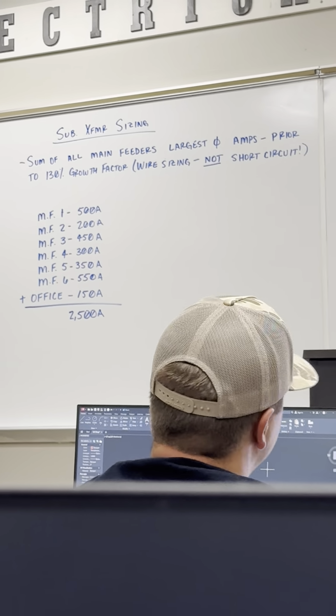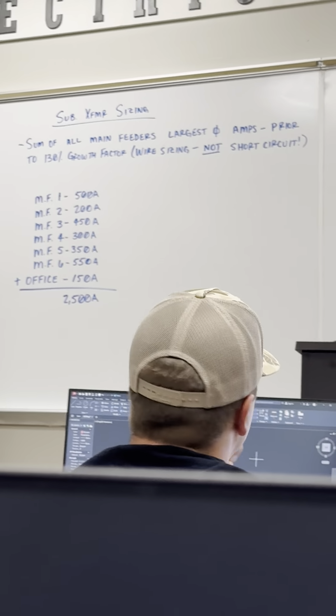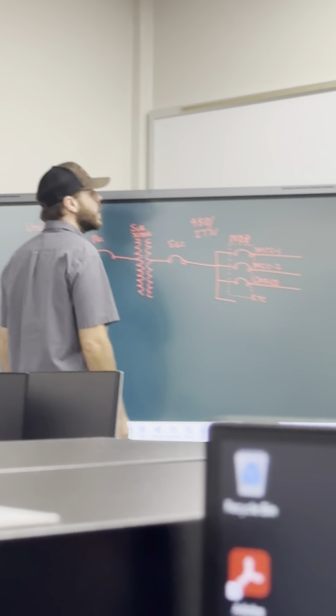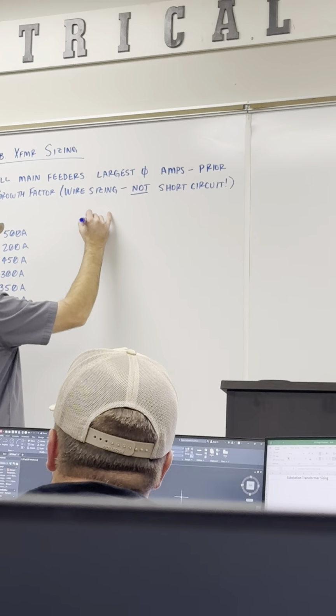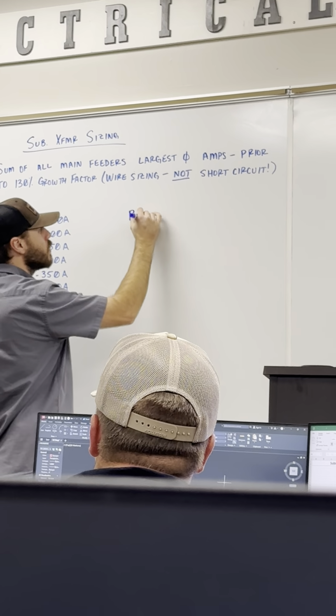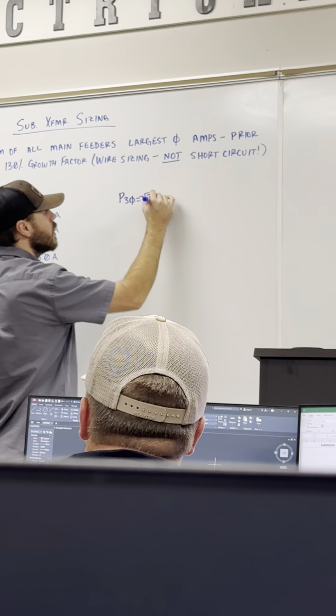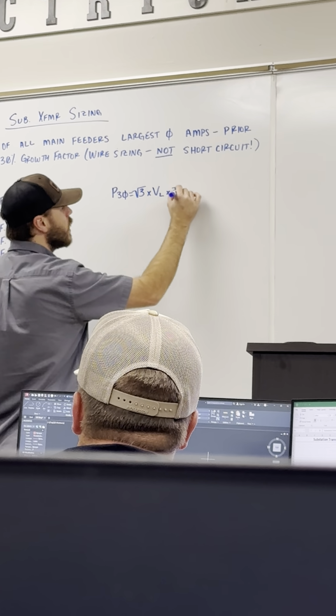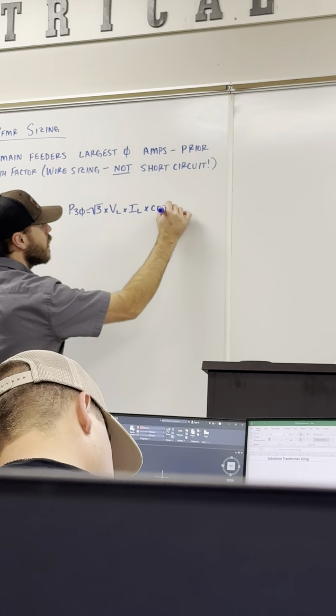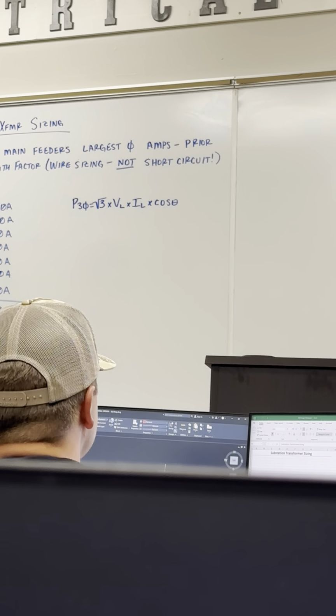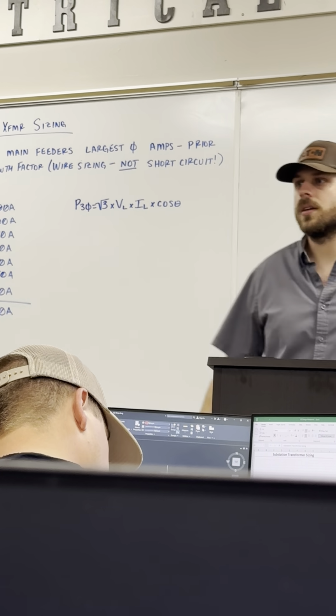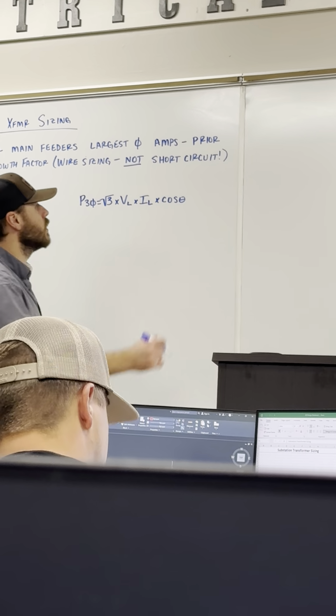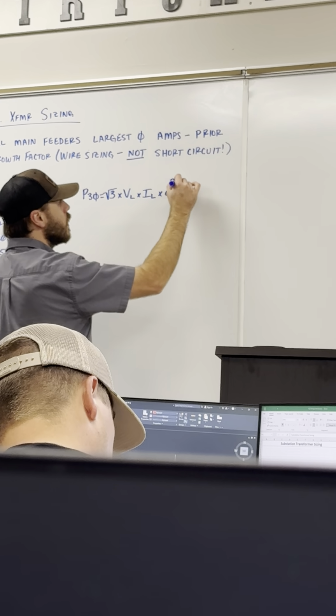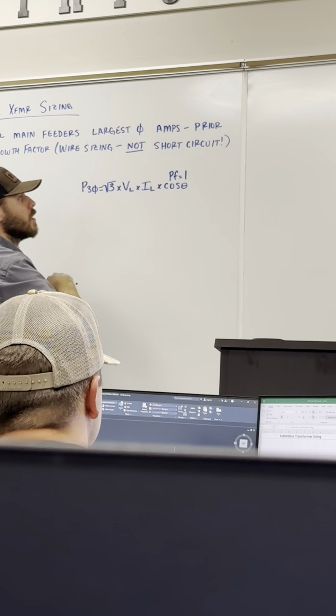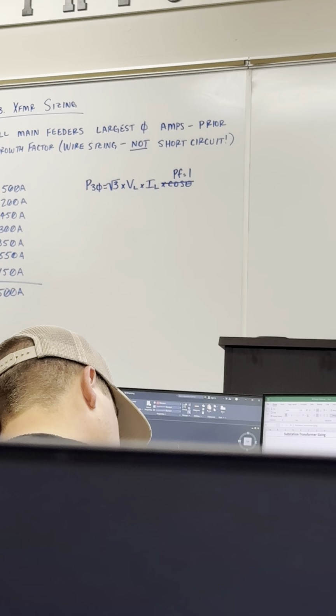Once we get all of this current added up, that's everything that's going to be flowing on this secondary side here. We also know voltage, so now we can incorporate that three-phase equation. Power in three-phase equals square root of 3 times V line times I line times cosine of theta. But we said for our project, our power factor is unity, right? So that's a numerical value of 1.